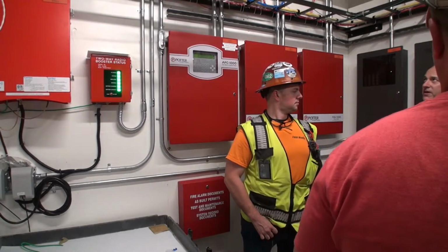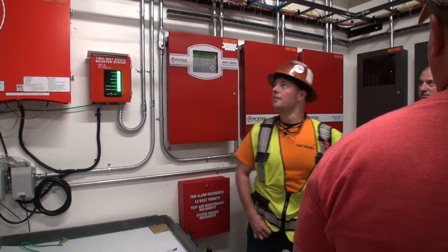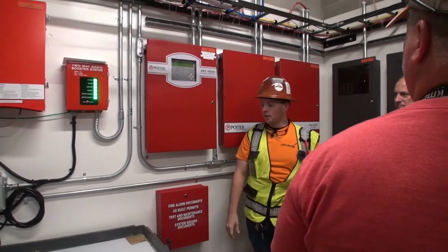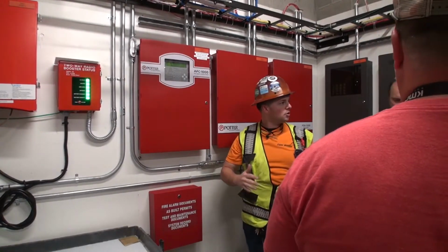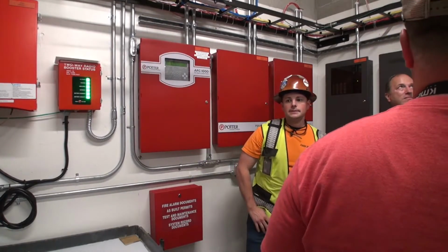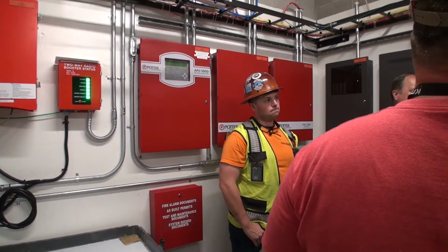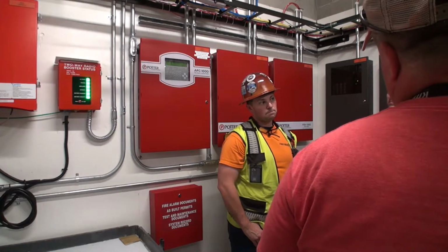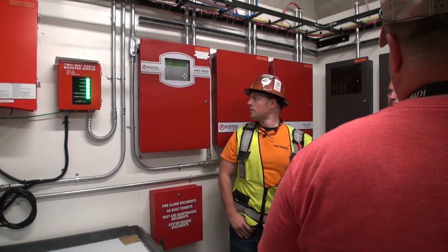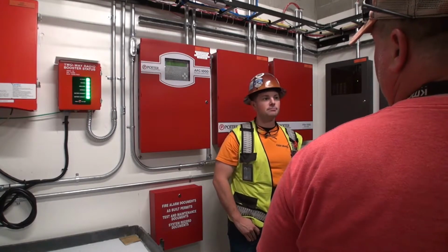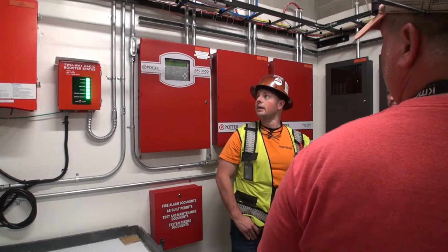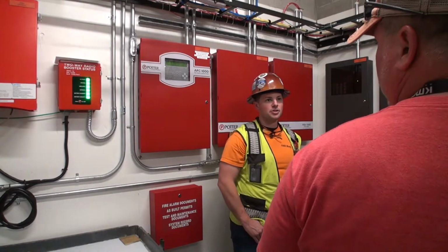And fault isolation. I believe every loop has isolation modules, multiple isolation modules, and they're all shown on the as-builts. Okay. Which parts of which SLC loops are on which isolators. You went through the addresses and whatnot as far as on the smoke detectors or strobes. Any initiating device that comes up with its location, that device should be blinking different from the rest, and it'll be marked with a loop and an address number that matches what shows up on the fire panel.